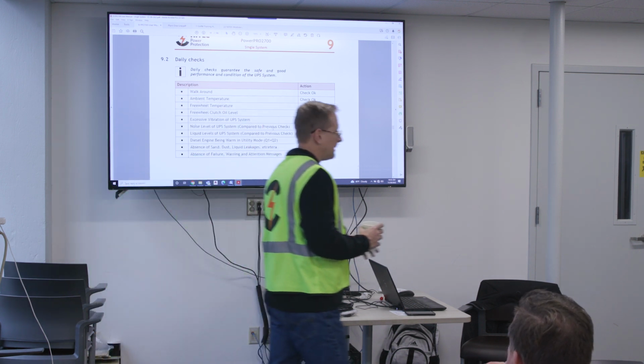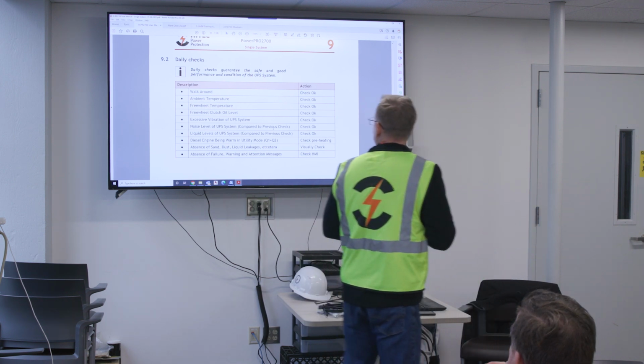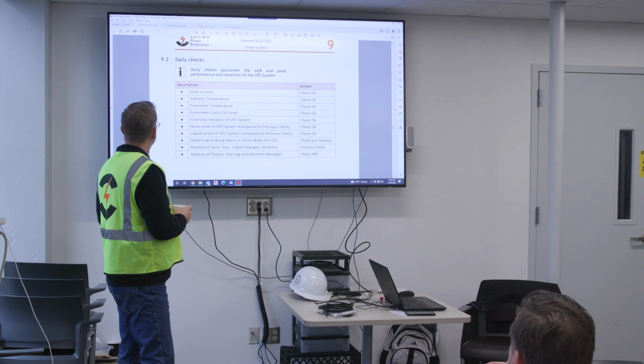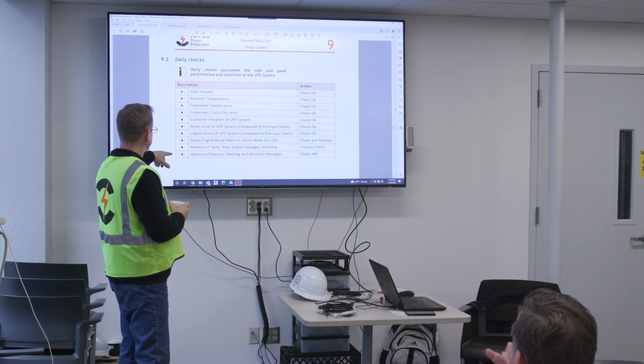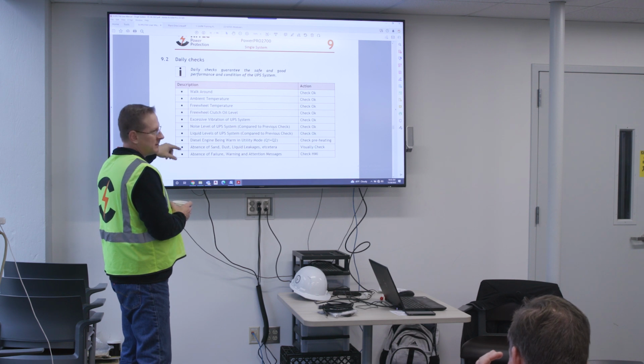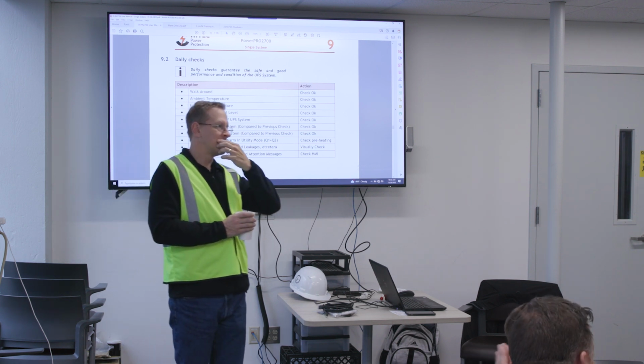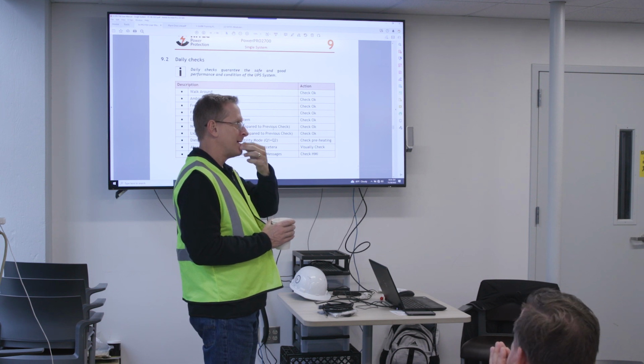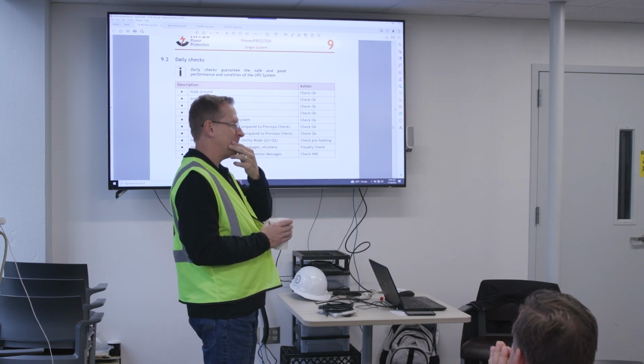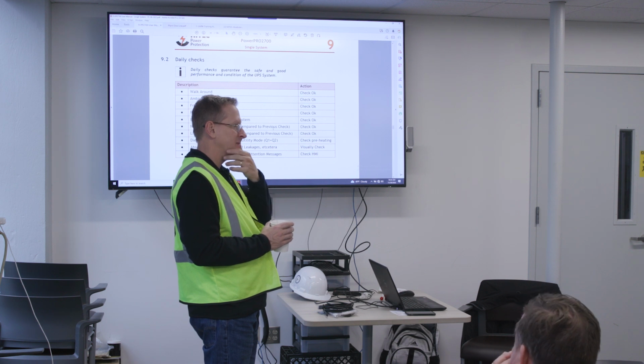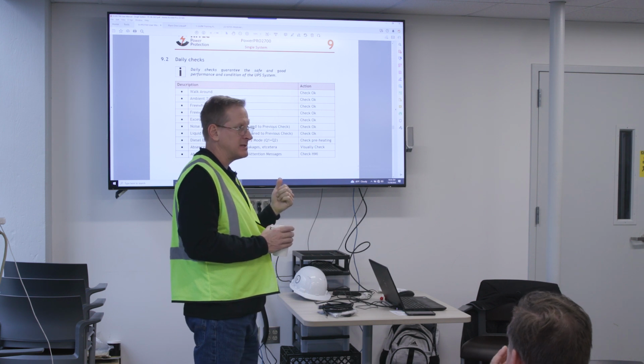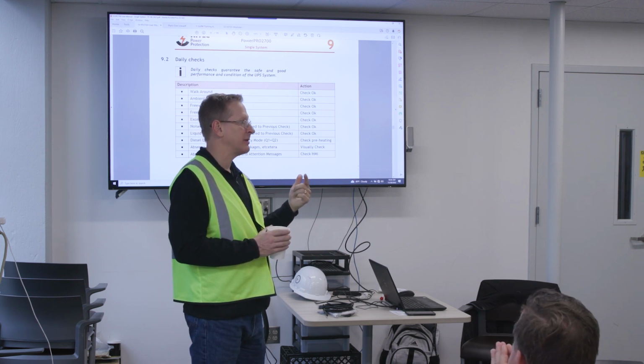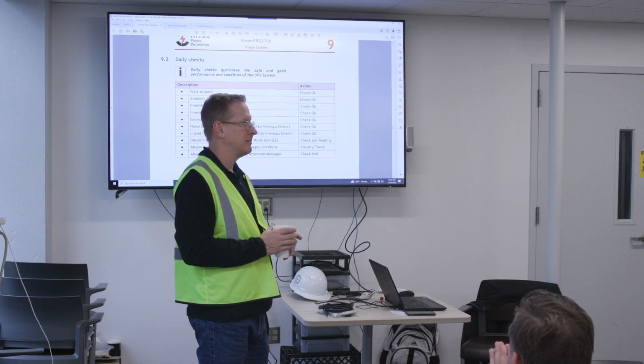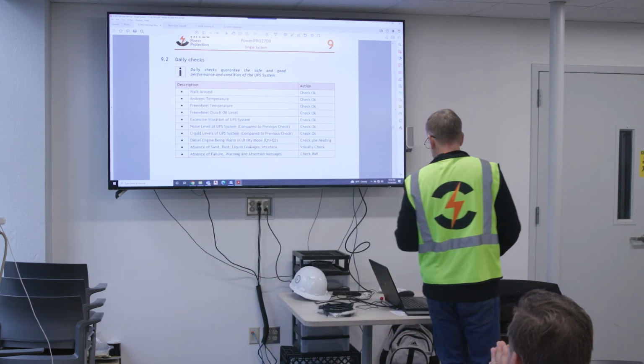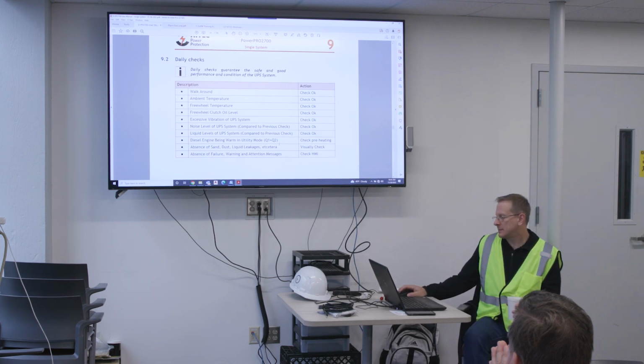I don't see oil temperature on there. It may not be on this list, but we do have an oil temperature reading downstairs. That was like 84 or 86, and my minimum was 90 on most rotating machinery. I'm not really sure what the range should be for a Cummins engine, but I do know that we have an alarm level in our HMI, plus the diesel also has an alarm level that will alert us if it gets out of range.